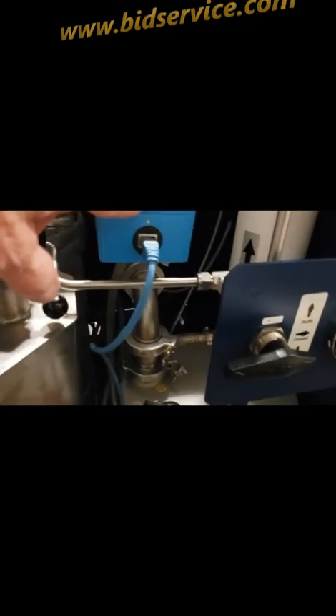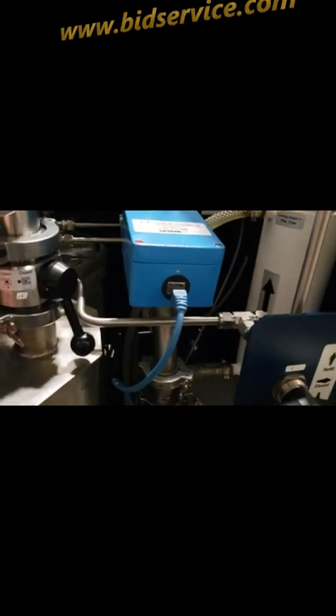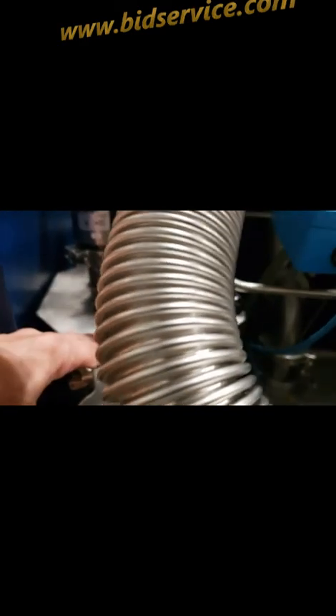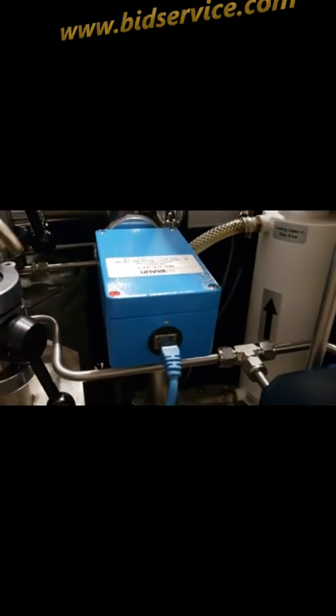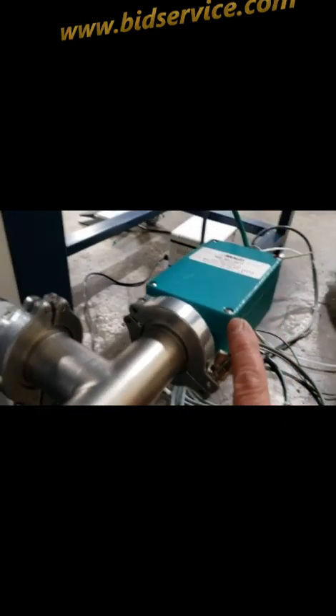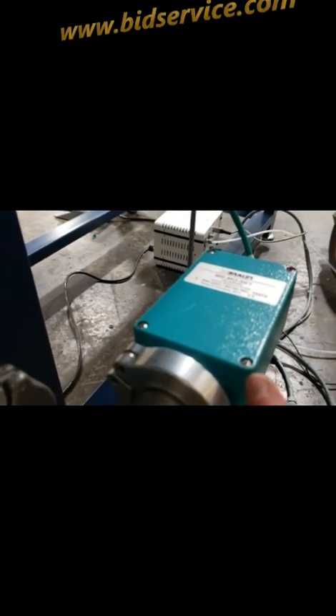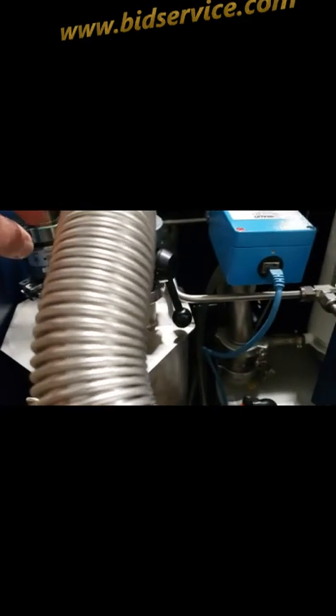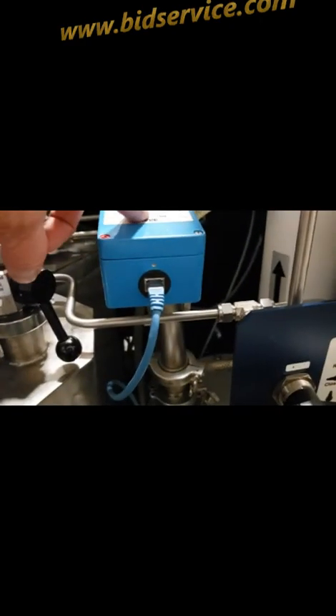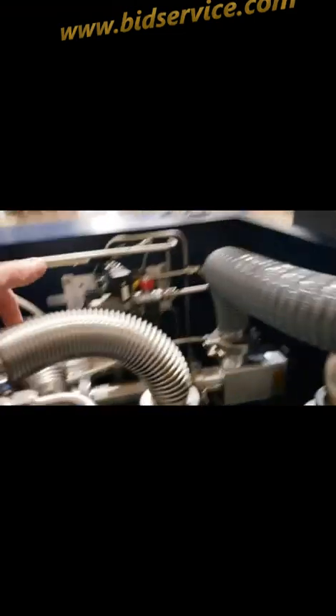As you can see, there's an oxygen sensor here. That is placed after the solvent trap. Then on the return of the gas, it'll go through, coming out the box underneath here, attached here, through this stainless steel line here. There's an oxygen sensor placed right here. Excuse me, that's the moisture sensor. Through this line here, through the solvent trap, past the O2 sensor, and then it leads into the purifier.